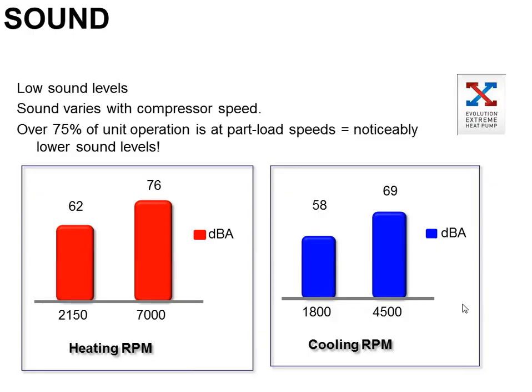Sound-wise, this guy is going to be a fairly quiet unit as well. Some of that's because of the sound technology put into the unit. A lot of it's because we're going to ramp him down. Both the compressor and condenser fan are going to be ramped down on low load scenarios. And most of the year, we're going to be at some kind of low part load scenario. So most of the year, we'll be running less than full RPM. So we'll be quiet most of the time. And this gives you an idea of the sound level differences if you want to look at that.